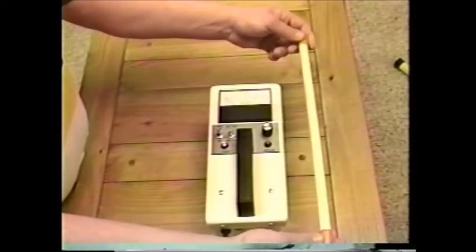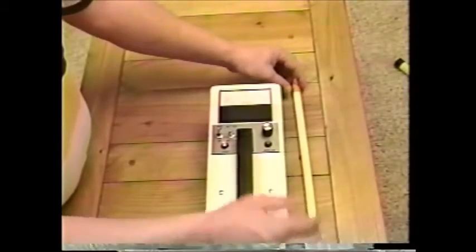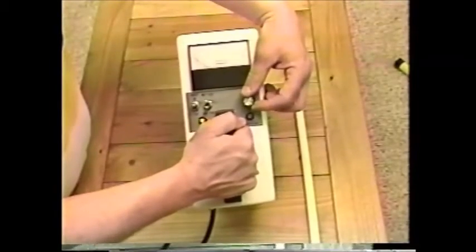The electrodes are spaced to test six inches of fiberglass at a time. To verify the tester is operating properly, a test bar is included. This is not for use in calibrating the unit, only for verifying that the unit is operating properly.